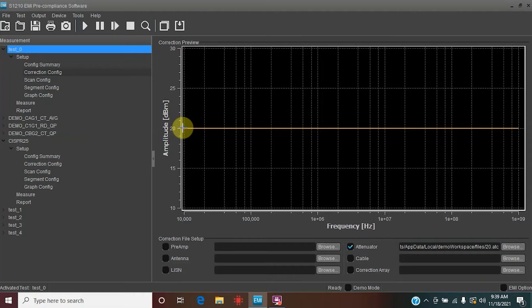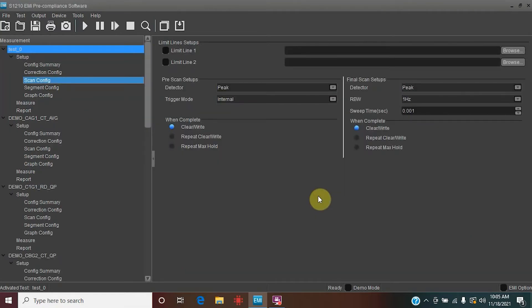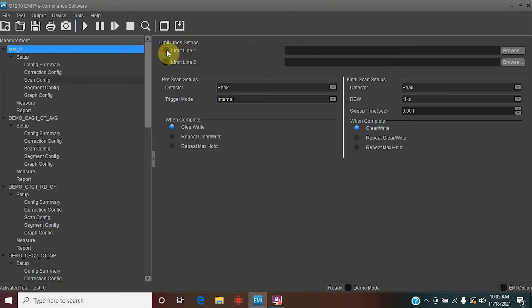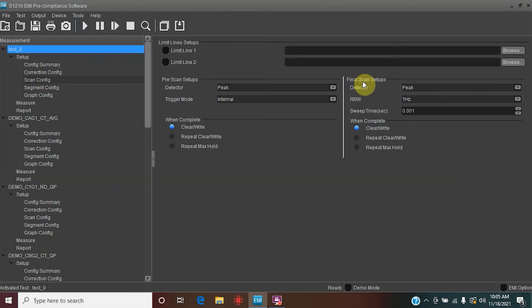That wraps it up for the correction file setup. Now let's take a look at the scan configuration and look at some of those limit lines. On the scan configuration section you will see the limit line setup in the upper left corner — same methodology as the correction configuration, allowing you to enable different lines and import different files. Below that you'll see your pre-scan setups, and to the right your final scan setup. We'll leave those defaulted at peak. Today we're really just concerned with limit lines.